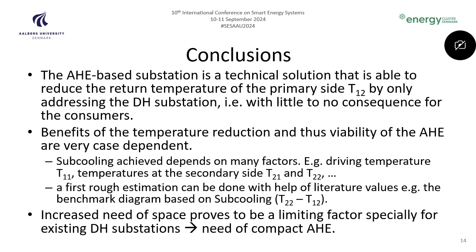Finally, the increased space need for the absorption heat exchanger, particularly in existing district heating substations, poses a significant challenge. There is a clear need for more compact designs to address this issue.